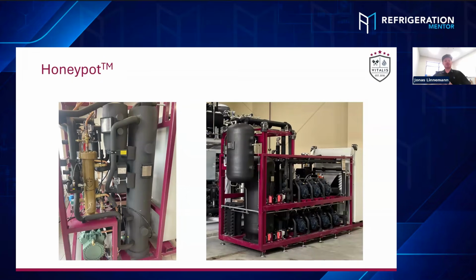So if you pull the vacuum of the entire system, you don't need to isolate the oil reservoir. Right? You just pull out the whole system with a vacuum, and you just use the chance that the system is under vacuum and still continuing to pull down to just connect the oil hose and fill the reservoir up. Perfect. And then the other way is when the system's actually running. That's when you need to isolate it, depressurize it, and then pull it in. Just want to make sure that everyone understands the steps when they're going to work on your equipment, the way to do it on a startup or when they're doing it on service. So we just want to be clear on that. So that's perfect. Thank you.